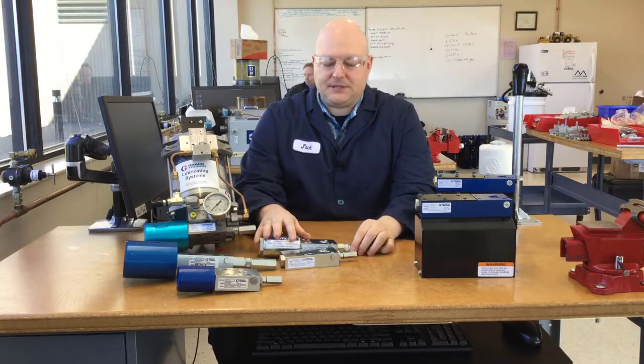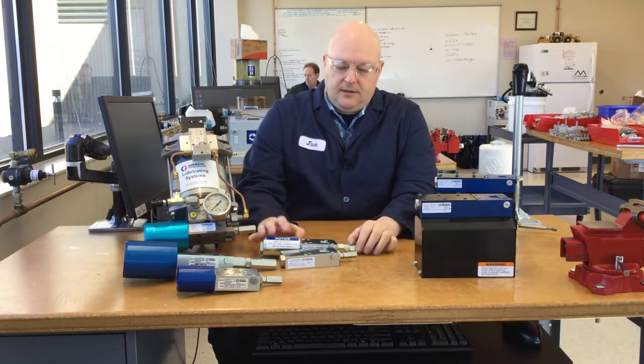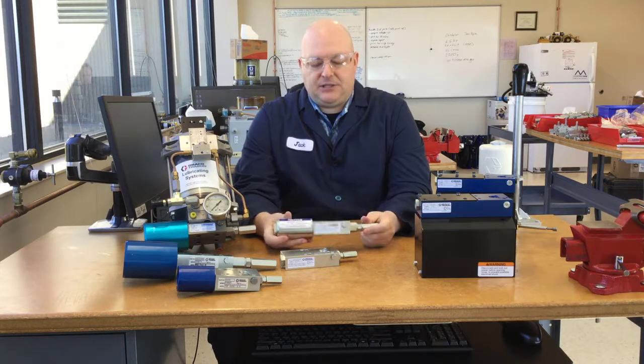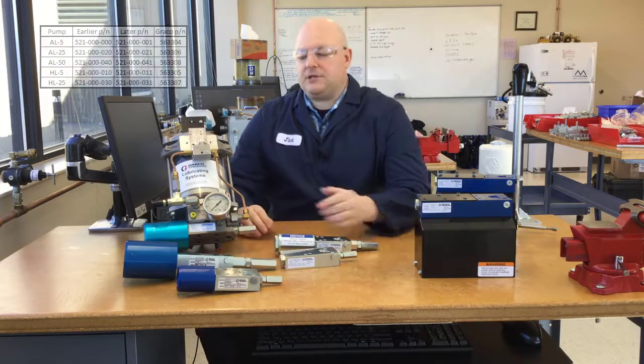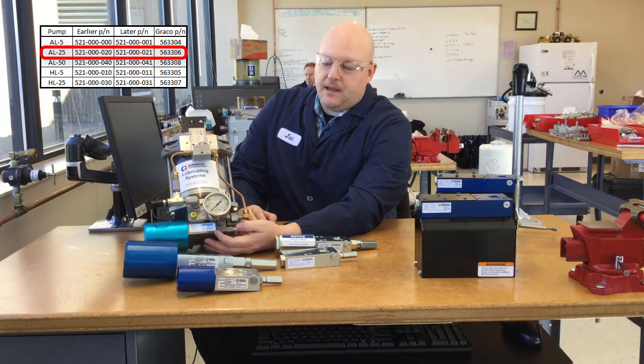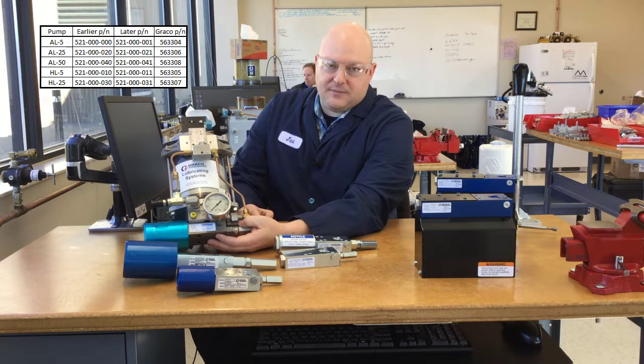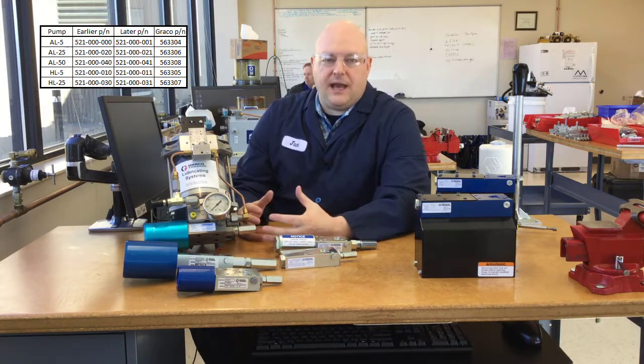With the pneumatic and hydraulic pumps, there was a change made in the mid-90s. On the old pumps, the bleed screw wasn't on the pump - it used to be up on the manifold - and there were a bunch of other internal changes. Externally they have the same dimensions, but those internal changes affect the repair kits. The old part numbers ended in zero; for instance, this old AL25 says 521-000-021 - if it was one of the really old pumps from before that internal change it would say 521 00020. When they made the internal change they renumbered everything up one.